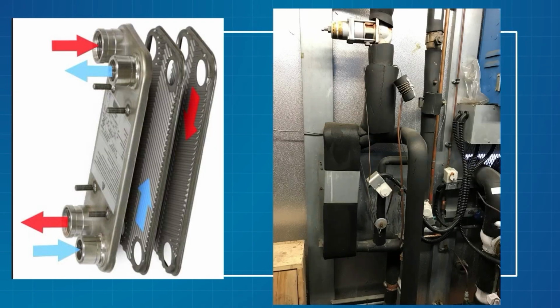Okay, so how does a subcooler work? There's a few different versions, but they're all very similar. They're plate heat exchangers, you've heard that term. This one is a brazed plate heat exchanger, you'll hear that term too. There's nothing unique about the heat exchangers we use on a subcooler, they're the same ones used widespread in the HVAC industry, for chilled water.